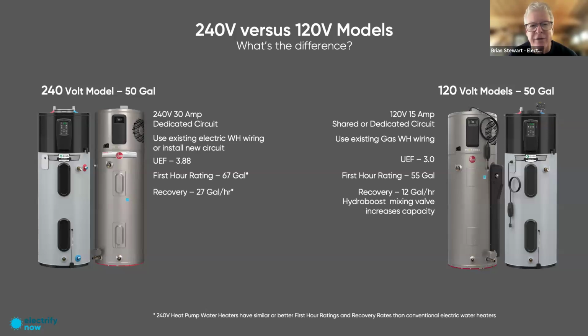But the bigger issue may be that the recovery rate is slower. For the 240 volt units, they can operate essentially just like an electric resistance model if forced into that backup electric resistance mode. The heat pump 120 volt ones don't have that, so you're going to be slower to reheat the tank.